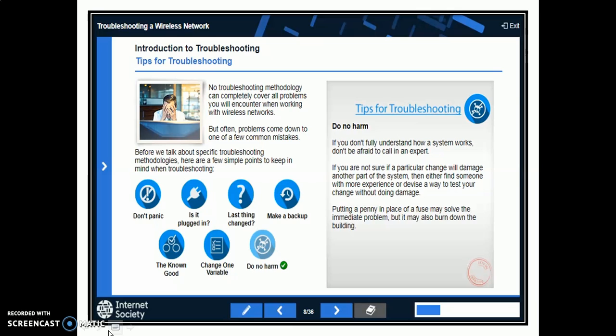The known good: you have to have a known good equipment, say for example a mounting cable. Say we are suspecting a cable might be faulty. So we have a known working cable that is tested and working. We can replace the suspected faulty cable with the working one and see whether the problem is resolved or not. If it is not resolved, we need to look at some other area. If it is resolved with our working cable, that means the problem cable was faulty.